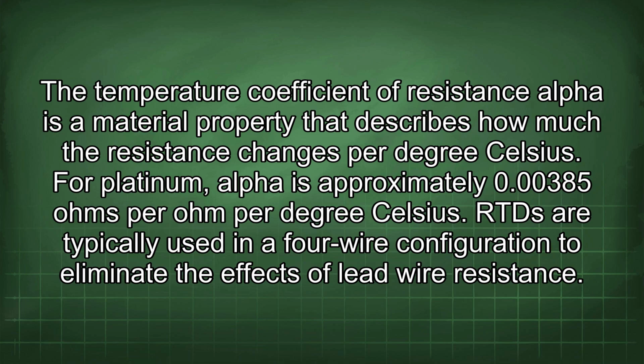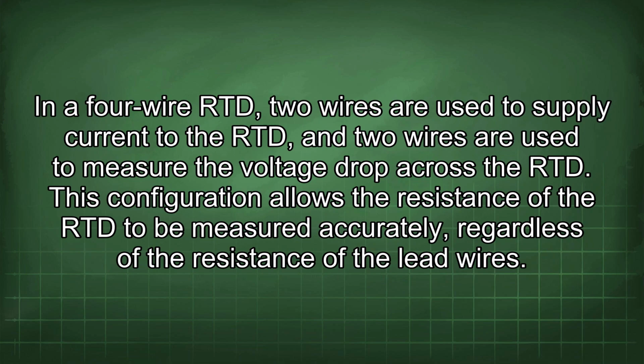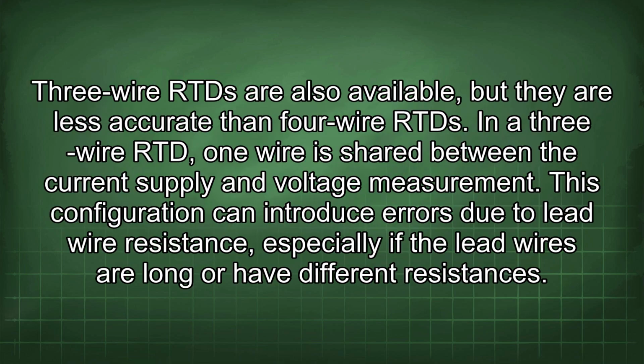RTD are typically used in a 4-wire configuration to eliminate the effects of lead wire resistance. In a 4-wire RTD, 2 wires are used to supply current to the RTD, and 2 wires are used to measure the voltage drop across the RTD. This configuration allows the resistance of the RTD to be measured accurately, regardless of the resistance of the lead wires. 3-wire RTD are also available, but they are less accurate than 4-wire RTD. In a 3-wire RTD, 1 wire is shared between the current supply and voltage measurement. This configuration can introduce errors due to lead wire resistance, especially if the lead wires are long or have different resistances.